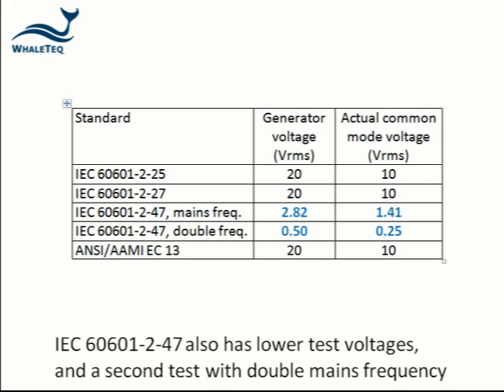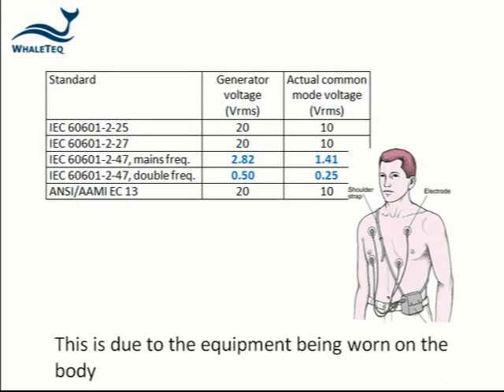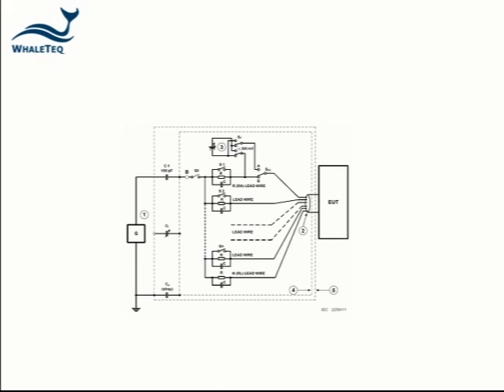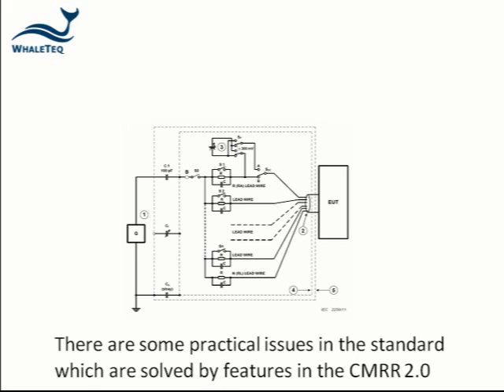In IEC 60601-2-47, the test voltage and frequency is different to other standards. This is due to the equipment being worn on the body. There are some practical issues with the setup in the standard, which are solved by some of the features in the WhaleTeq CMRR box.